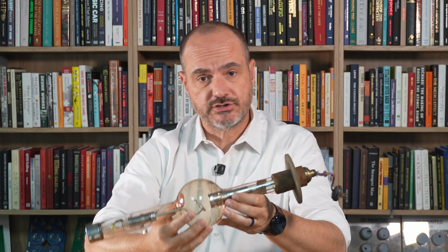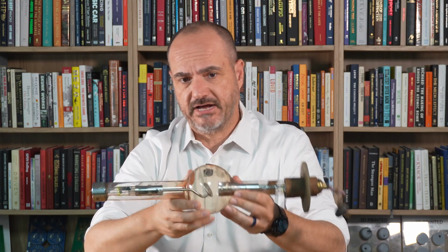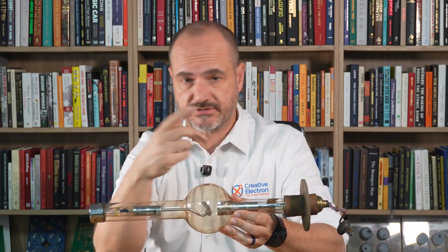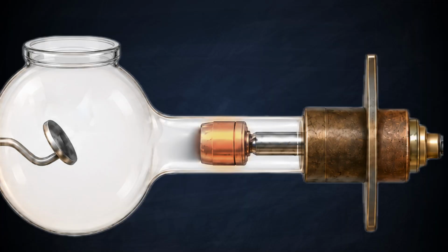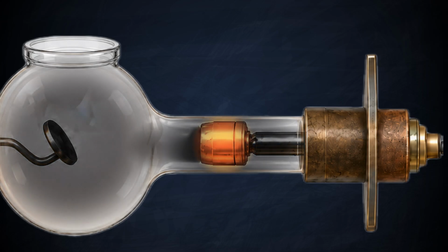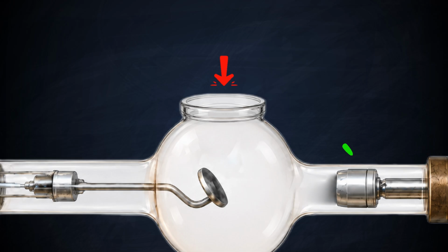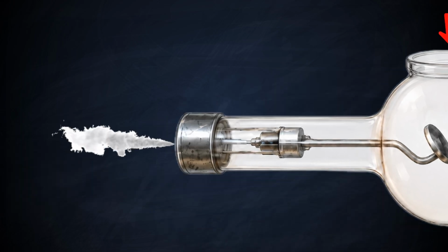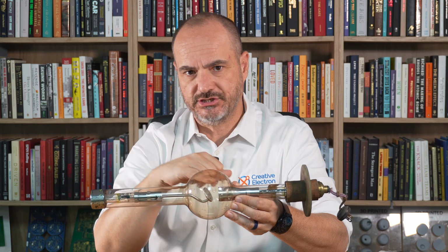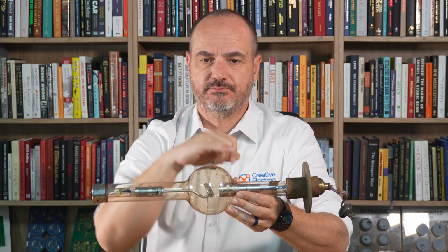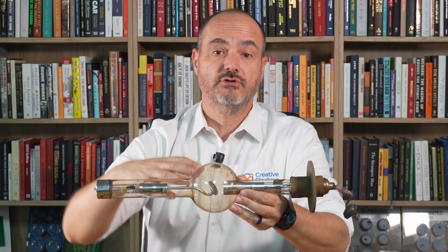Because from the closed tube, the failure mode of these devices is the filament eventually breaks because it gets warmed up, cools off, warmed up, cools off, and you have all this thermal cycle on the filament. Eventually, it ruptures and the closed tube has to be replaced. On open tubes, you can replace the filament yourself. But once you replace the filament, you have to close the tube again and apply vacuum, right? Because those electrons can't see any oxygen molecules or nitrogen atoms between the filament and the target. So you do have to apply a vacuum before you can use the tube again.